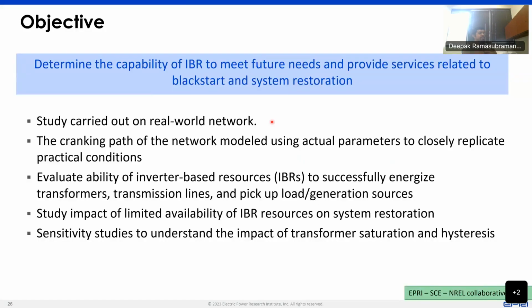It was a collaborative effort with EPRI, SCE, and NREL. The aim of the study was to understand the capability of an inverter-based resource fleet to provide these services of black start and system restoration, for a cranking path that was evaluated for a real network. So we had this real network cranking path, and we had to evaluate whether the inverter-based resource fleet could really energize the various sections of the network and pick up the generator on the other side of the network.